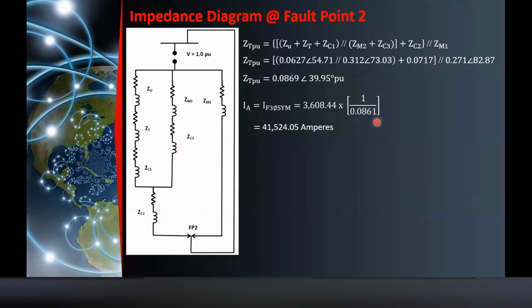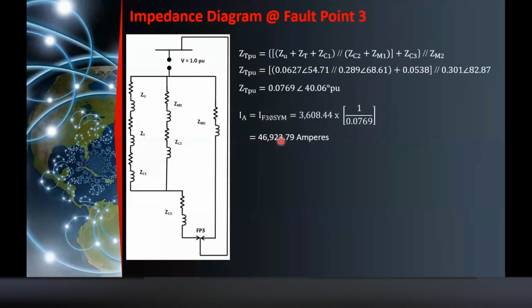Okay? Then, ganun ulit ang gagawin mo. You will find your I per unit. This is VPU divided by ZTPU. So, you will get 41,524.05 ampere. So, pag nagkaroon pala ako ng fault dito, dapat ang rating ng circuit breaker ko, interrupting capacity, is minimum 41,524.05 ampere. So, hindi ko na kinumpute dito yung asymmetrical. Pwede yung basis yung una. Simple lang naman yung diagram natin.